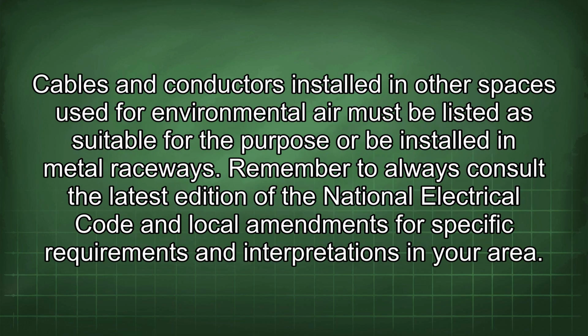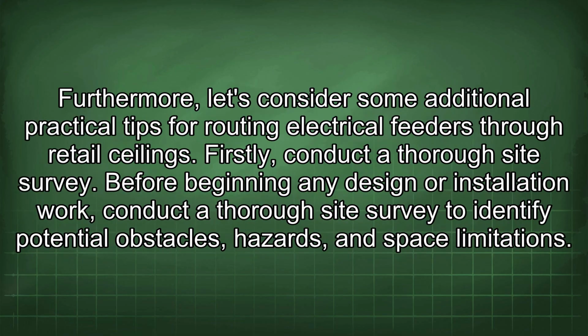Cables and conductors installed in other spaces used for environmental air must be listed as suitable for the purpose or be installed in metal raceways. Remember to always consult the latest edition of the National Electrical Code and local amendments for specific requirements and interpretations in your area. Furthermore, let's consider some additional practical tips for routing electrical feeders through retail ceilings.